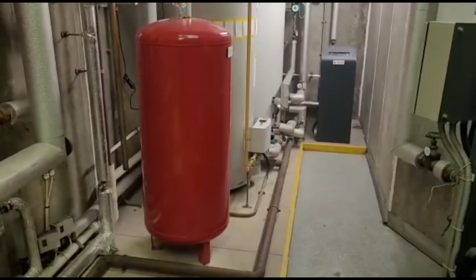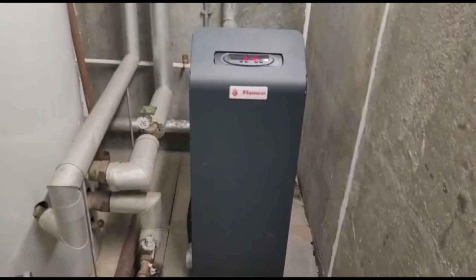Obviously got this pressure vessel, and then we've got these water heaters. They should be getting ripped out this year, I'm having new ones fitted. Had a new pressurization unit put in last year - that totally screwed up and over-pressurized the system and flooded out the plant room because it had the wrong PCB in it when they fitted it.